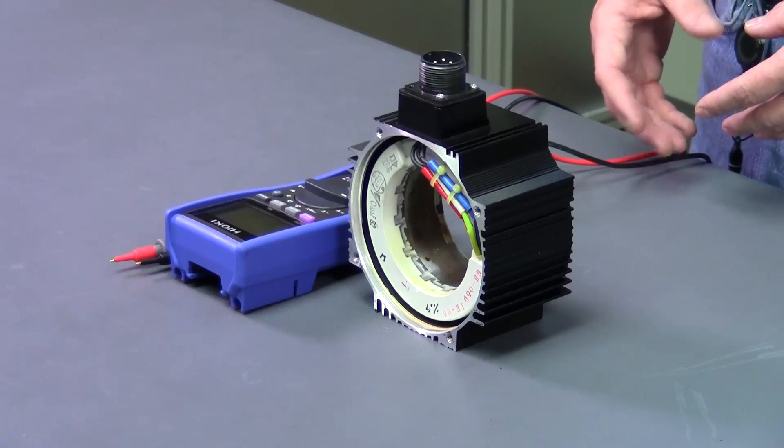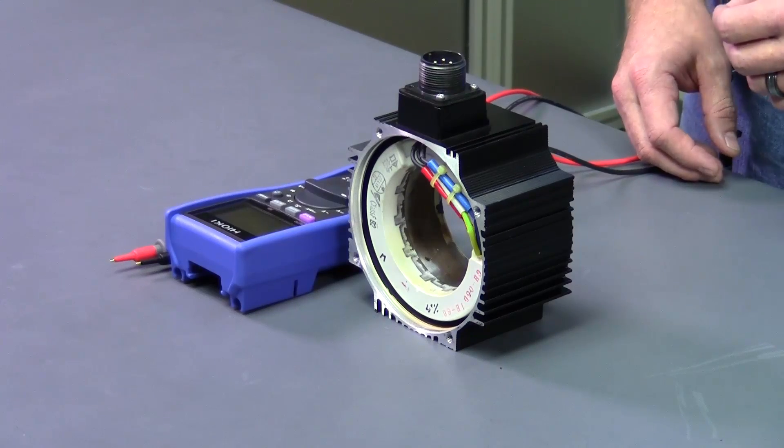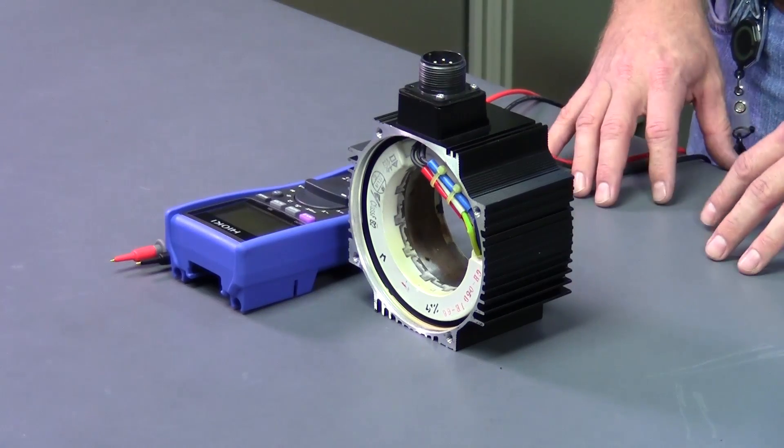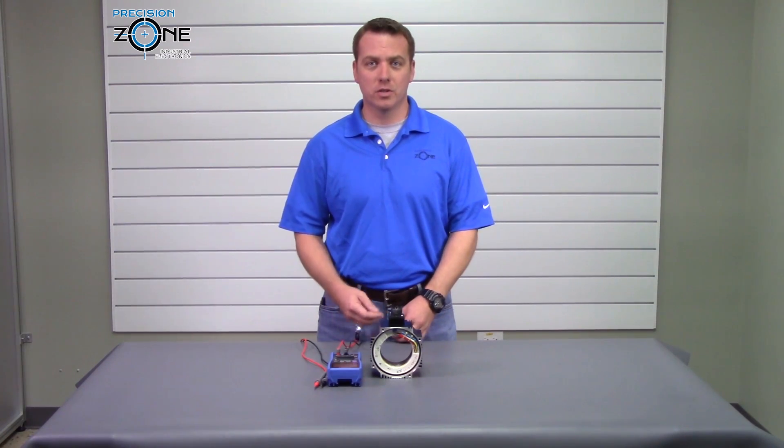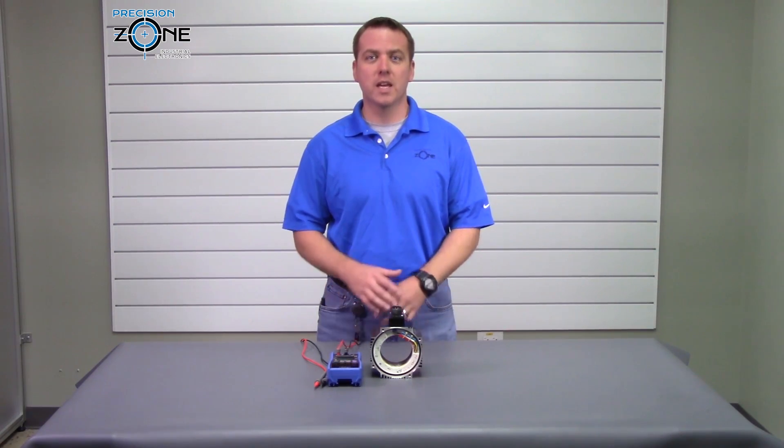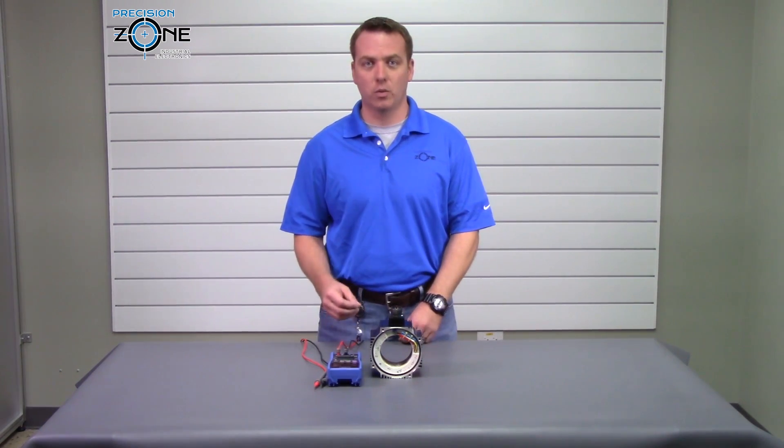Here at Precision Zone we use an SKF Baker that performs a phase-to-phase resistance, mega-ohm, high pot, and a surge test. This gives us a complete analysis of a stator winding.